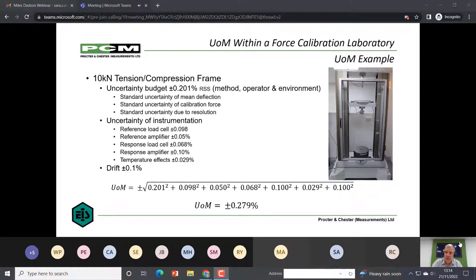As a worked example, here is one of our electromechanical calibration frames. It's a 10 kilonewton tension and compression frame. First of all, we have the uncertainty budget of the machine. This is a physical assessment of the method, the operator, the environment, and the physical setup of a calibration. This gives you the root sum of the squares, in this case just a smidge over 0.2%, and comprises the standard uncertainty of the mean deflection, the standard uncertainty of the calibration force, and the standard uncertainty due to resolution. So that gives you the physical aspect of conducting a calibration.